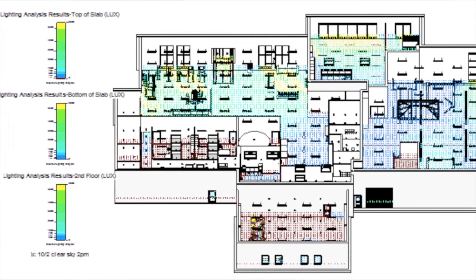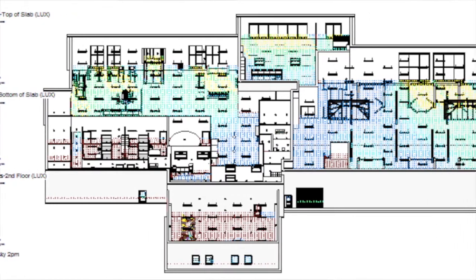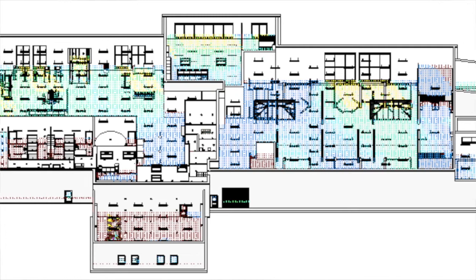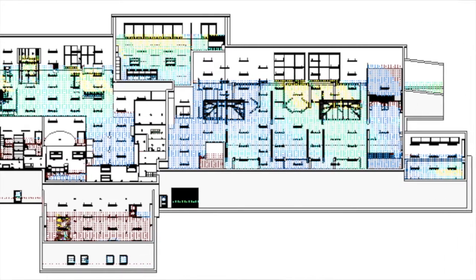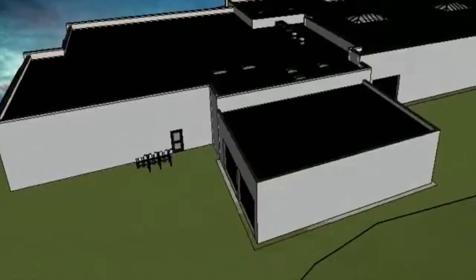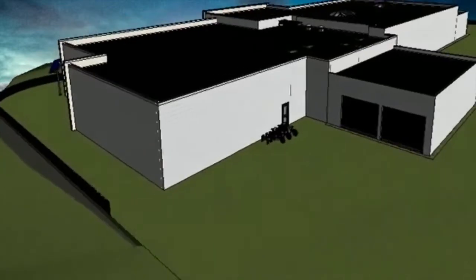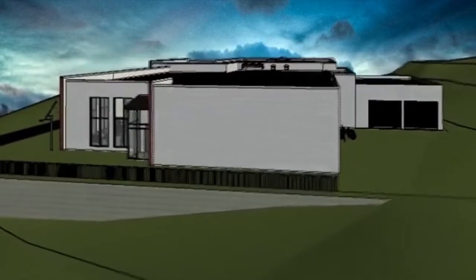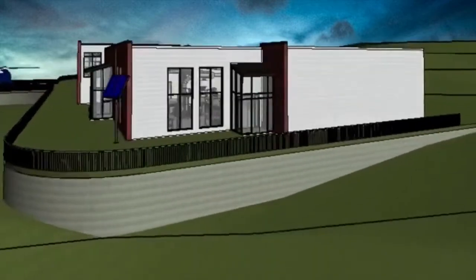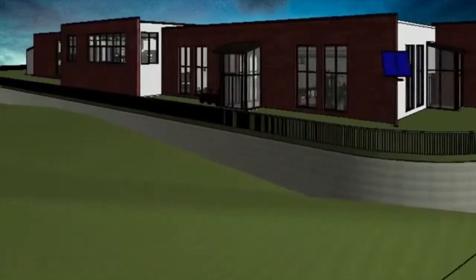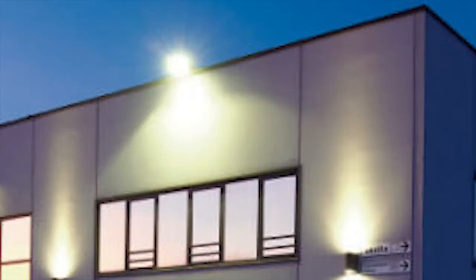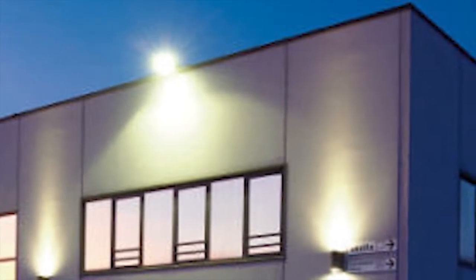Simulations were used to determine the best lighting environment for the building, and we compared different lighting fixtures like fluorescent, incandescent, and LED. We used the standards to determine which power densities were appropriate for each zone. Based on that, LED were the ones selected. For the external lighting, one of the things we needed to keep in mind was light pollution, and we based our selection on the standard of the International Dark Sky Association. The light fixtures that were chosen needed to meet those standards, and most of the lights are going to be LED, with motion control so they turn off automatically if there is no one there.